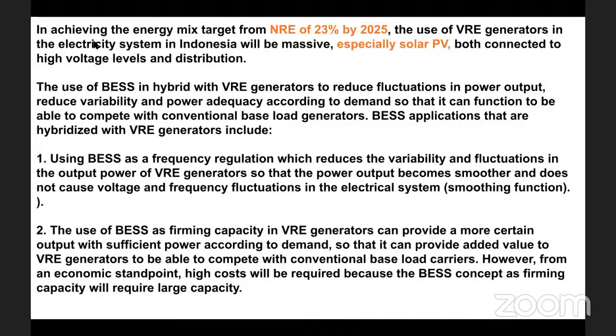In achieving the energy mix target from NRE of 23% by 2025, the use of VRE generators in the electricity system in Indonesia will be massive, especially solar PV, both connected to high voltage level and distribution. BESS is used in hybrid with VRE generators to reduce fluctuation in power output, reduce variability, and provide power adequacy according to demand, so that it can compete with conventional baseload generators.